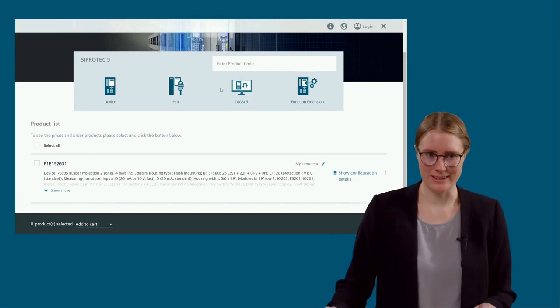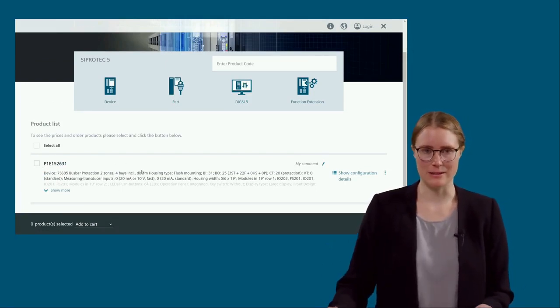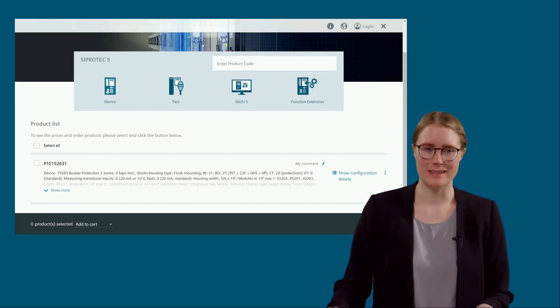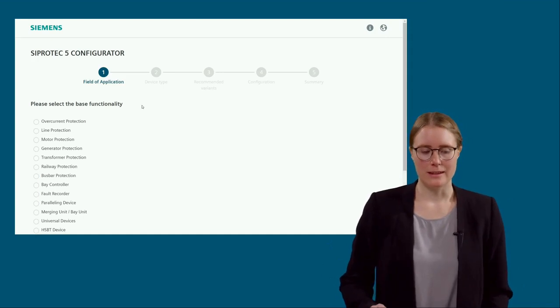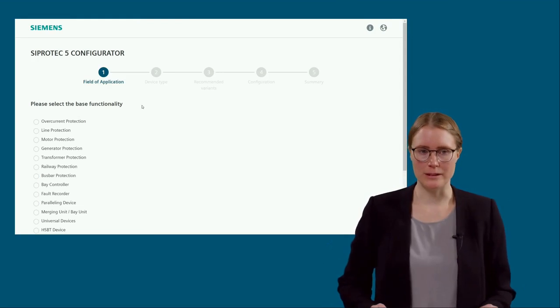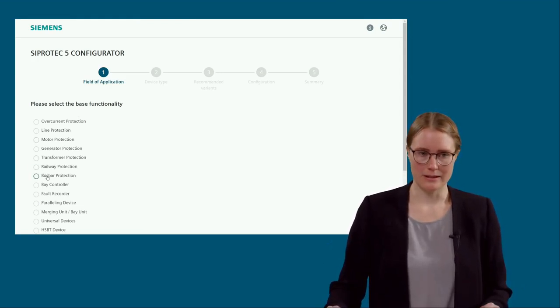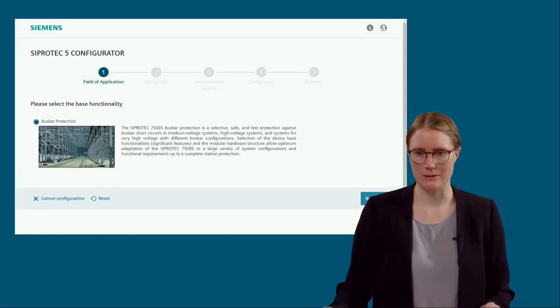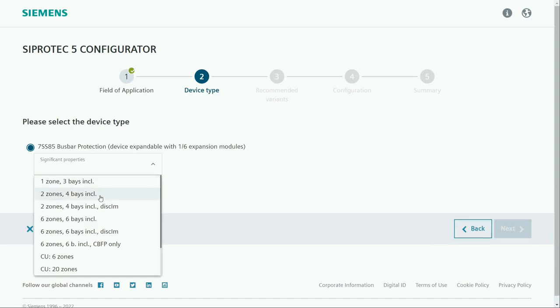Okay, so here we are, start again. Down here you see a list of the devices you already selected, but we start all over again with a new device. In this step, I want to configure the device for an IEC 61850 compliant solution in a fully distributed setup. So I start once again with the 7SS85, and in the second step I will select the corresponding merging units for the setup. I go with Busbar Protection again, jump over this description, and in this case we need exactly the same significant feature as before, because the first 6 are relevant both for the centralized setup and for the IEC 61850 compliant solution. I go with 2 zones, 4 bays and the disconnector image.